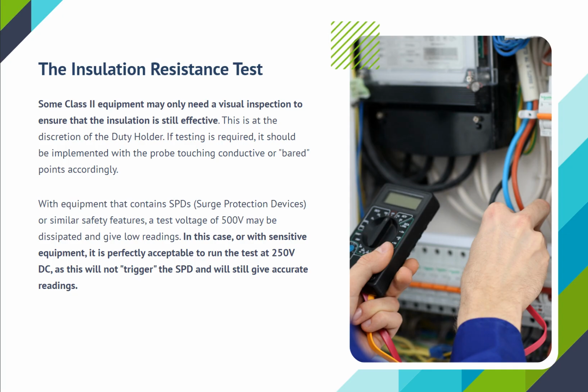With equipment that contains SPDs, surge protection devices, or similar safety features, a test voltage of 500 volts may be dissipated and give lower readings. In this case, or with sensitive equipment, it is perfectly acceptable to run the test at 250 volts DC, as this will not trigger the SPD and will still give accurate readings.